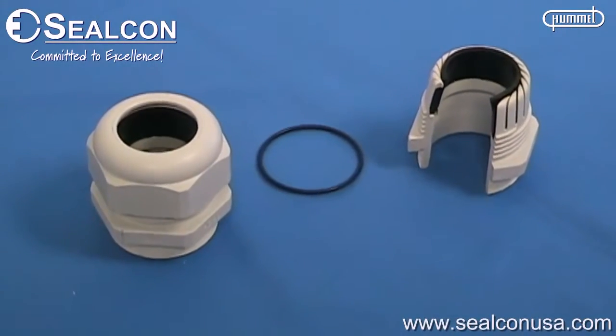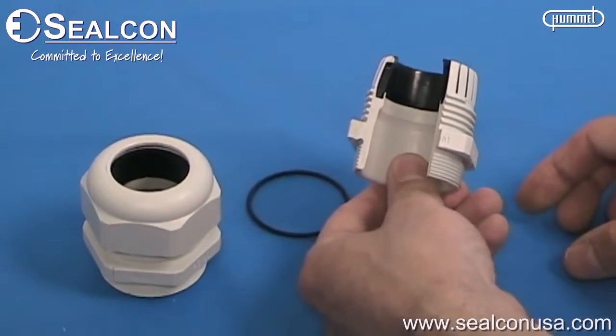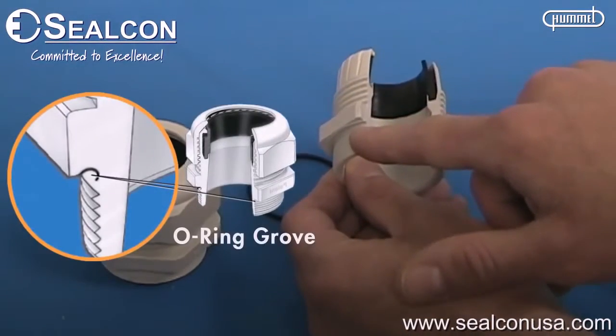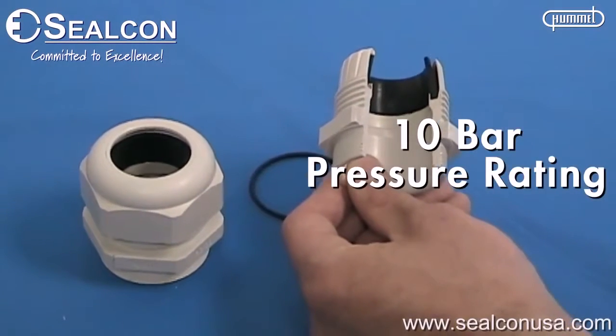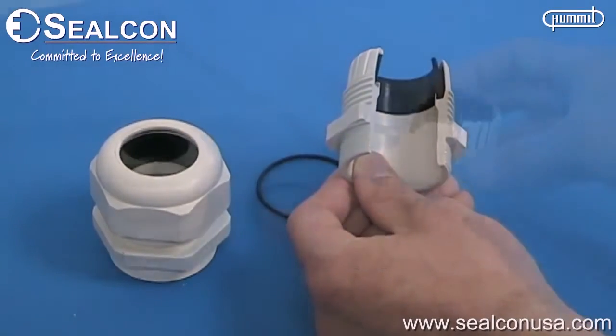Sealcon provides the highest industry standards for IP and pressure ratings. The lower recess in the form seal and O-ring groove, located on the installation thread side, allow an unsurpassed 150 PSIG or 10 bar pressure rating, as well as a NEMA 4X, N6, or IP68 rating.